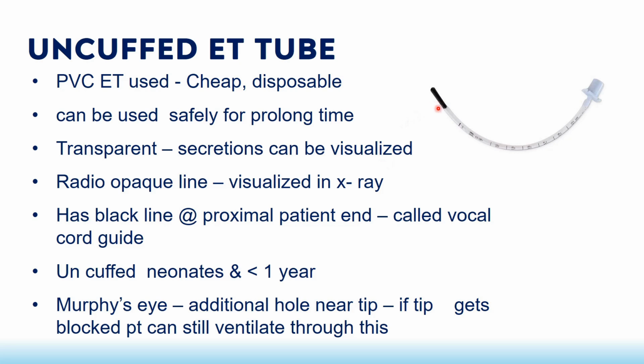And there is a Murphy's eye. This is one additional hole, the same as in the cuffed endotracheal tube. Here also there is a Murphy's eye, that is a lateral opening. The advantage of this additional hole is that it allows ventilation if the tip is getting blocked. Sometimes the tip gets blocked. So when the tip is blocked, the patient can still ventilate through this Murphy's eye.